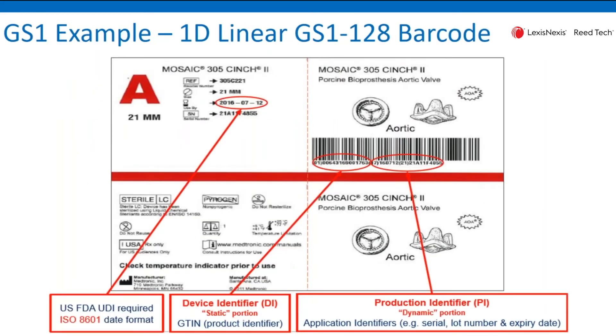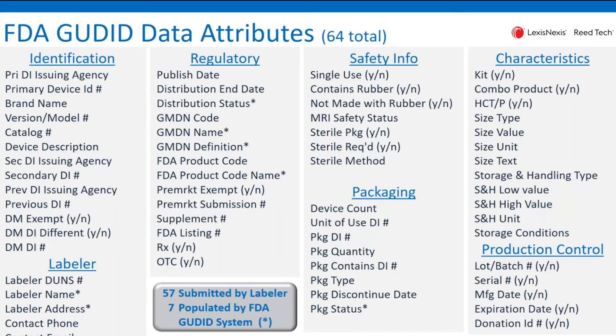Here's another example of UDI being placed on a medical device label — this one happens to be the one-dimensional barcode — showing the difference in the presentation of that data and the content. When you compare that to the data attributes that need to be reported, there are a number of attributes categorized by identification of the product, the labeler, regulatory information, safety information, packaging, various characteristics of the medical device, and production control attributes — all of these particular attributes need to be submitted to the FDA. This does present somewhat of a challenge in collecting that information and making sure it's clean and ready for submission.